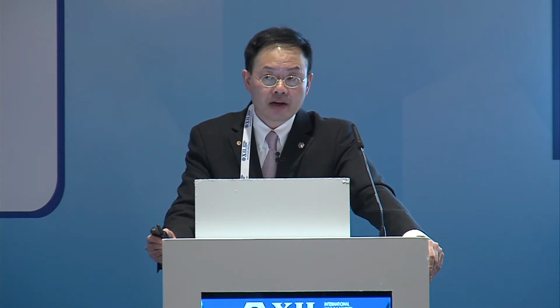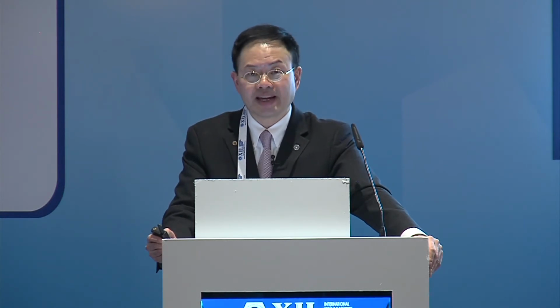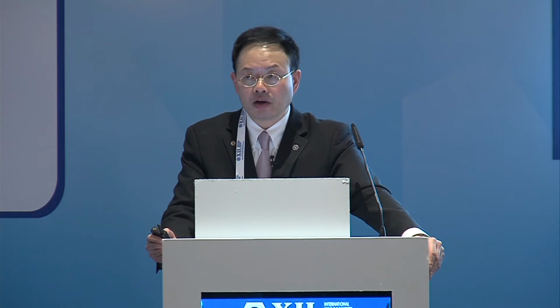Because there are two key elements that impact the room pressure design. One is the offset volume. The higher the offset, the higher the room pressure. The smaller the offset, the lower the pressure differential. The other very important element, which is typically ignored, is what we call the air tightness. For a very leaky room, you cannot hold as much pressure as you want. But for a very tightly constructed room, you can hold a much higher positive and negative pressure for the very same offset flow. So air tightness is another key variable in room pressure control design.